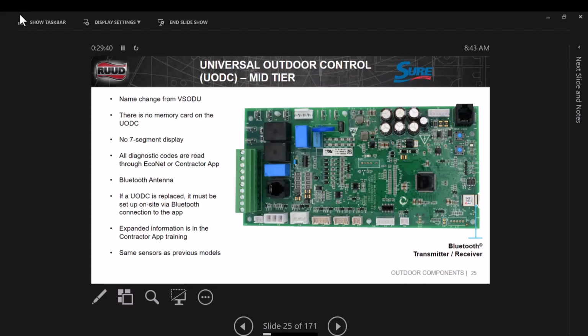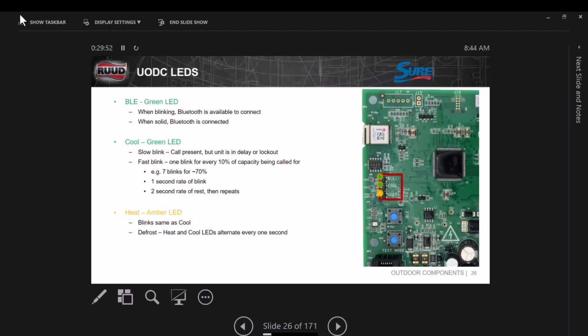It's pretty easy. All the sensors on our system, we didn't change the plugs, we didn't change the sensors. They're all interchangeable. The LED lights on the board, these are not diagnostic lights. These are lights telling you what the board is doing, whether it's in cool, whether it's in heat, what speed it's running at, or the capacity. As you see, the green light there is connected whenever we have a Bluetooth. So this is the Bluetooth light. Whenever you have a connection on Bluetooth, it turns solid. Whenever there's no one connected to it, it's blinking.